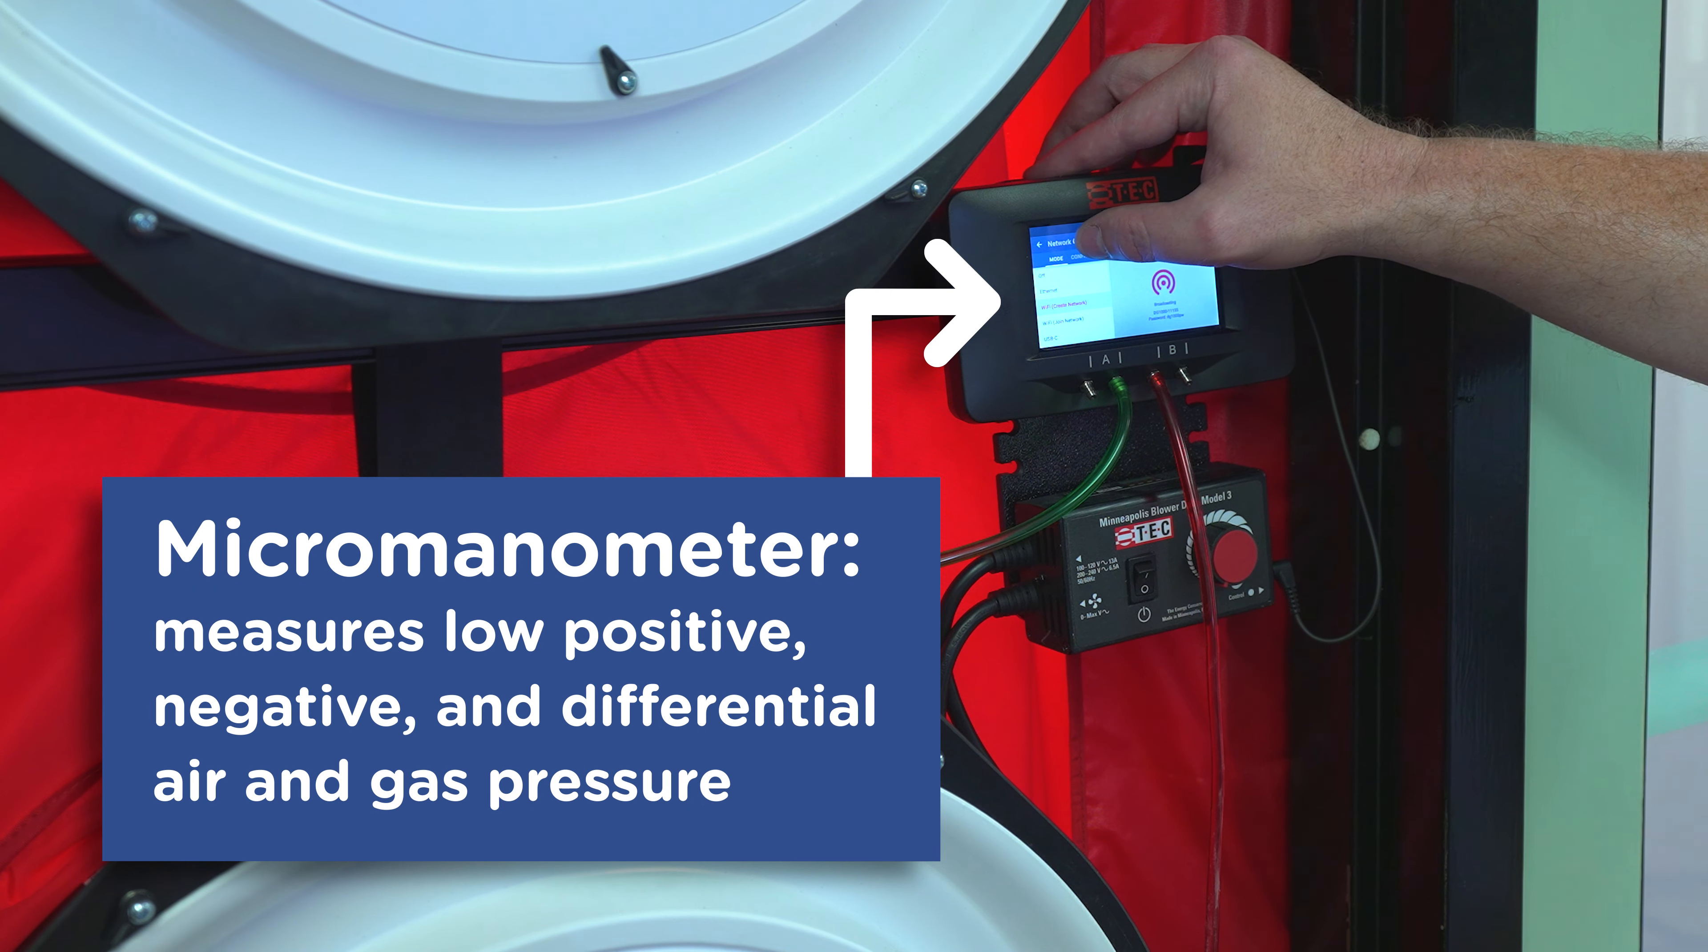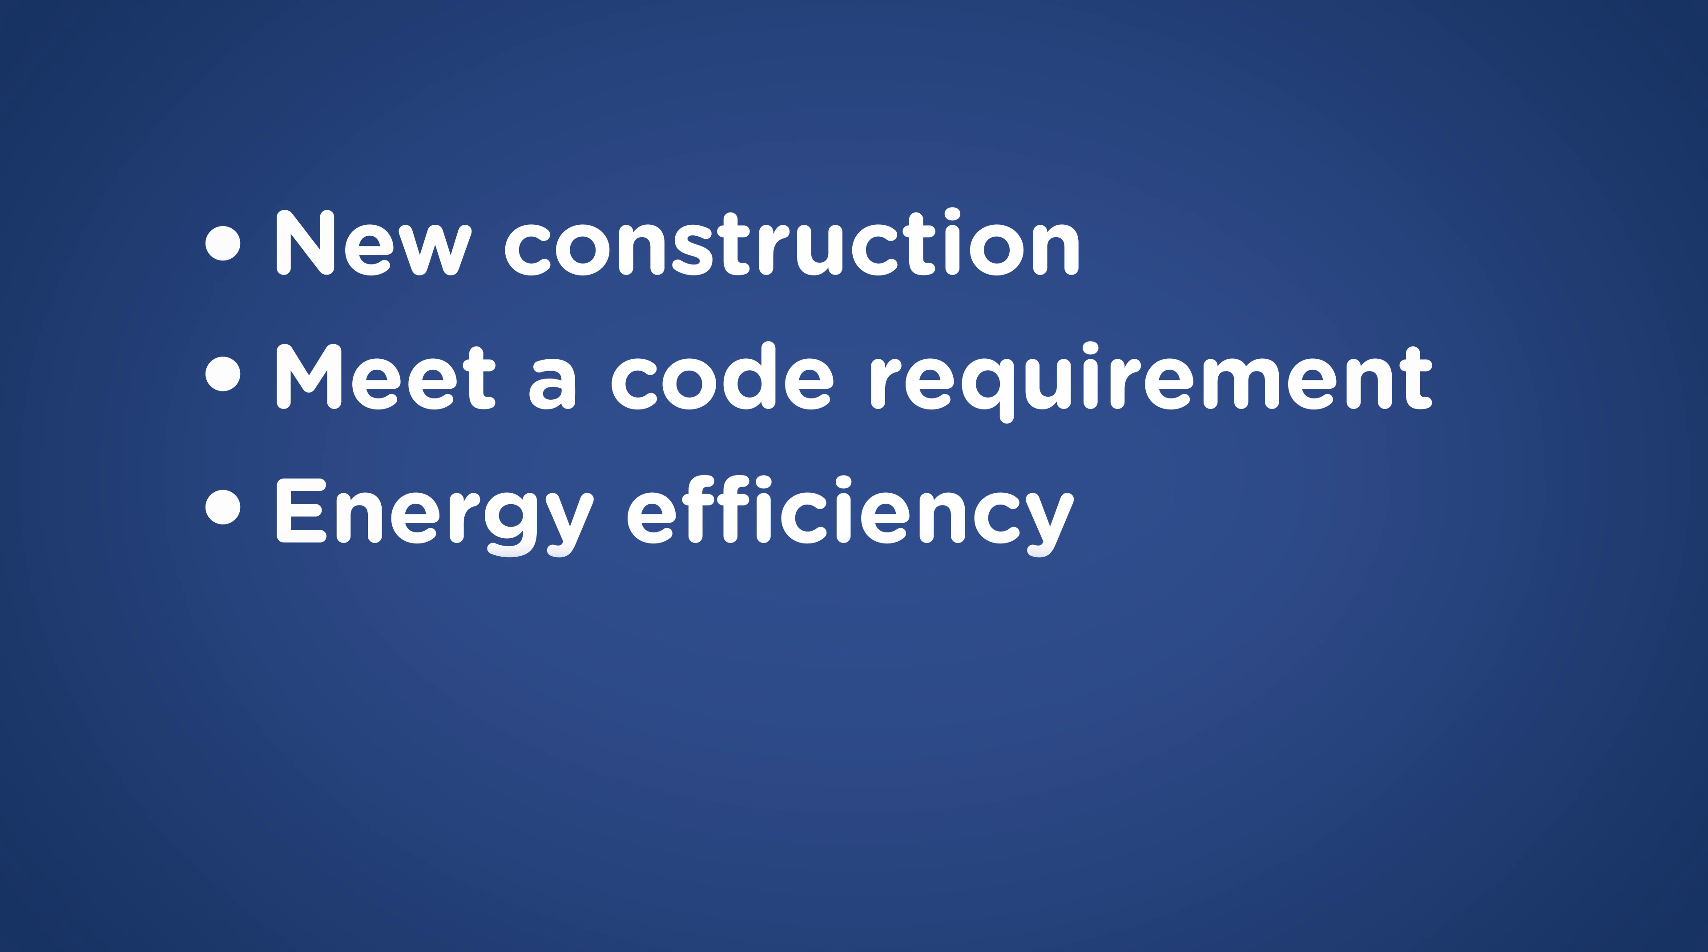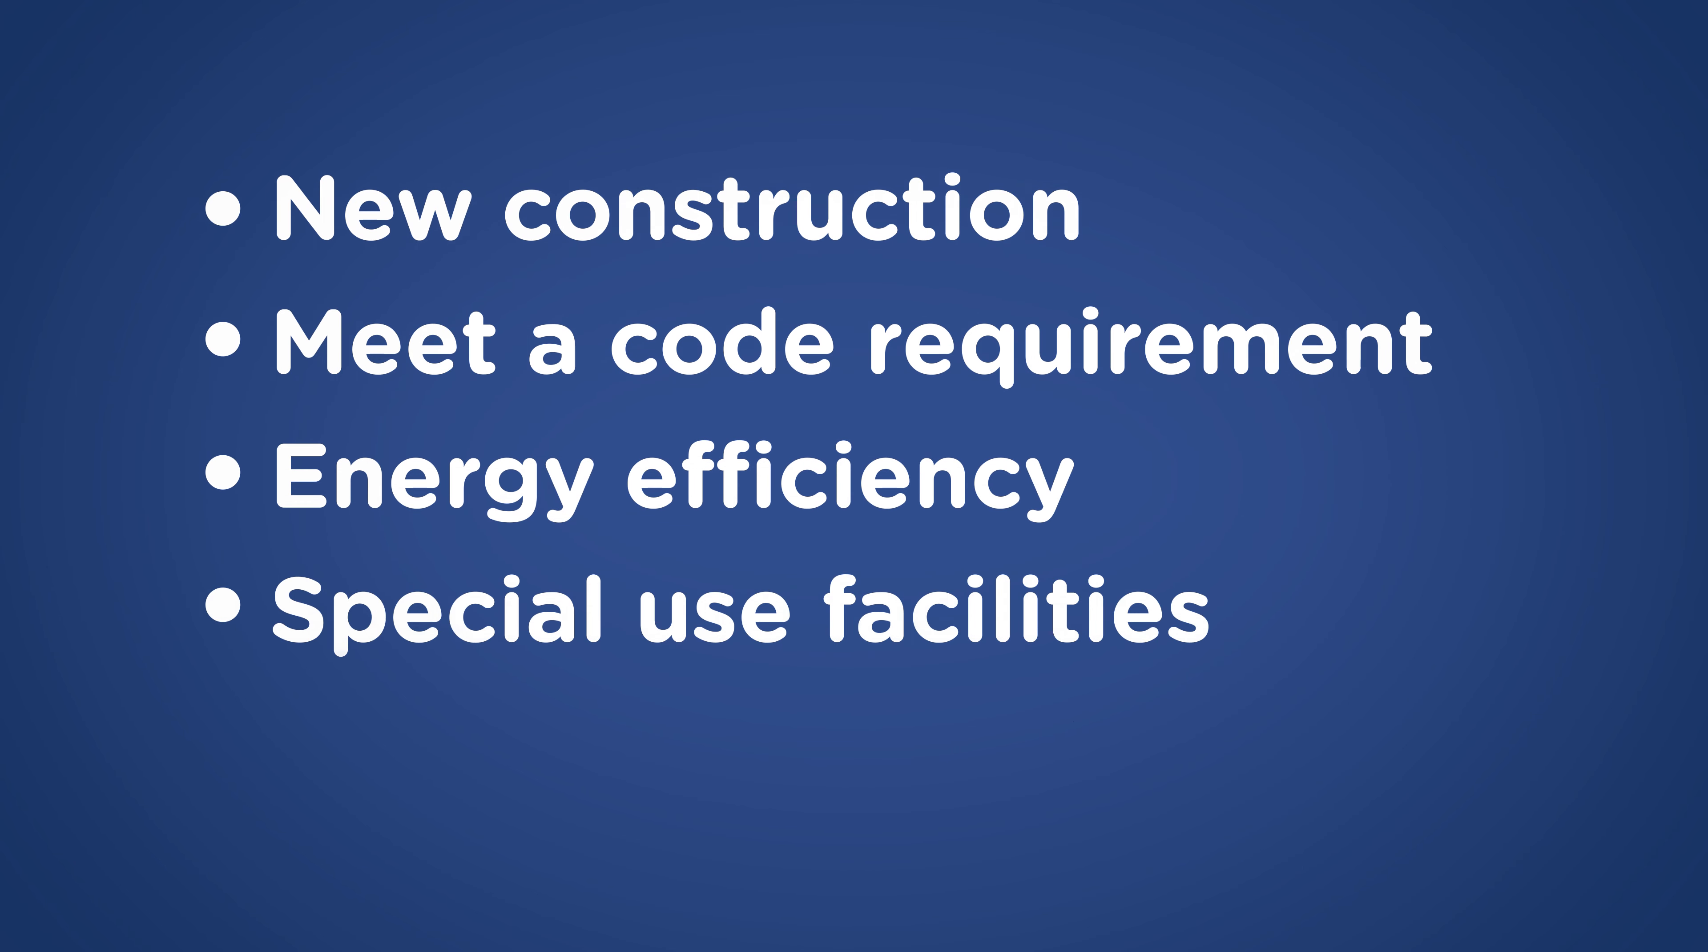Here you can see the setup. We have three blower door fans set up within a frame and shroud, along with a micromanometer that is used to measure the differential pressure between the interior and the exterior as we control it with the fans. Everything is hooked up to a laptop where we will be recording the data and measuring the air leakage of this building.